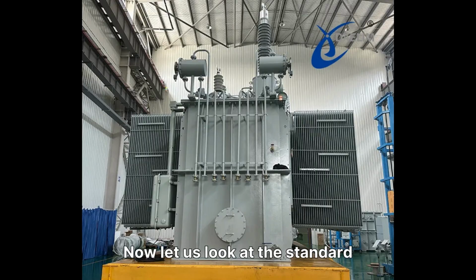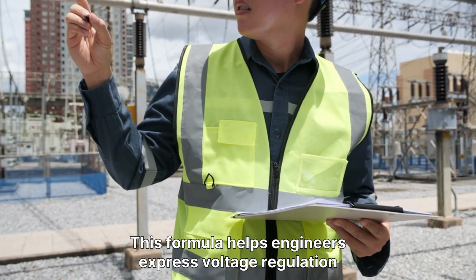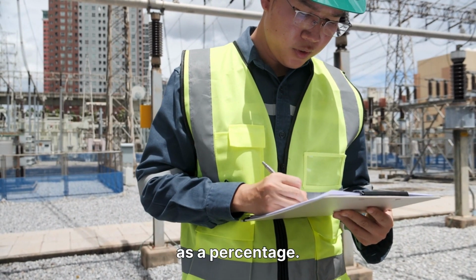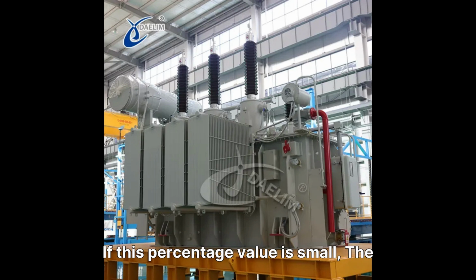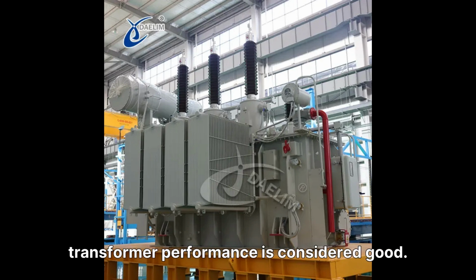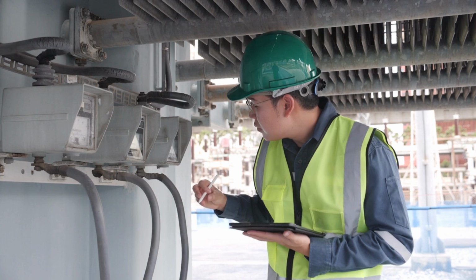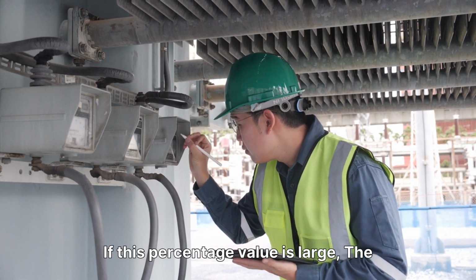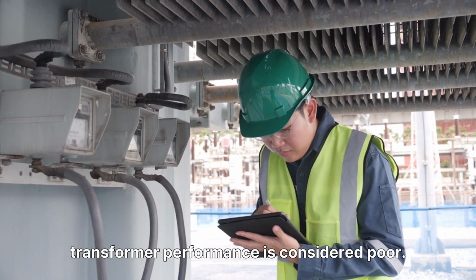Now let us look at the standard formula for voltage regulation. Voltage regulation is equal to no load secondary voltage minus full load secondary voltage, divided by full load secondary voltage, and multiplied by 100. This formula helps engineers express voltage regulation as a percentage. If this percentage value is small, the transformer performance is considered good. If this percentage value is large, the transformer performance is considered poor.